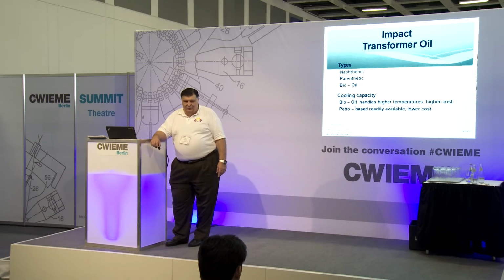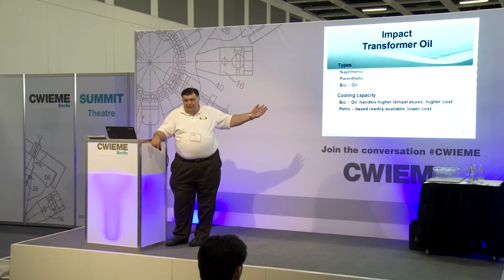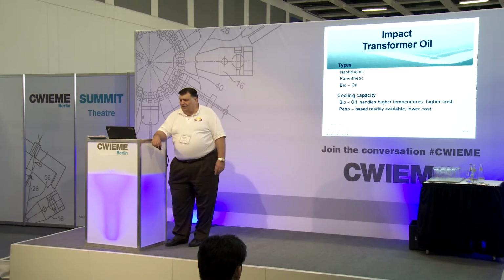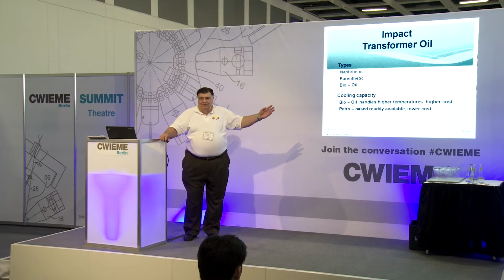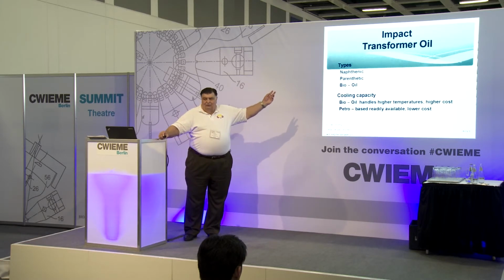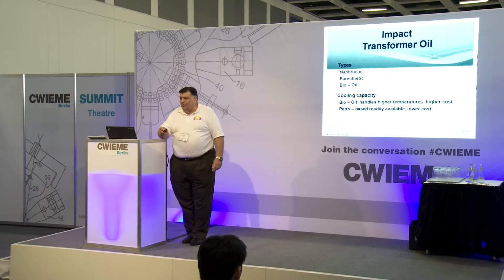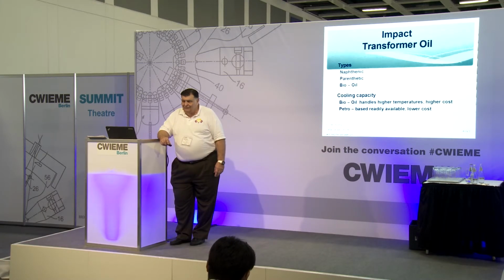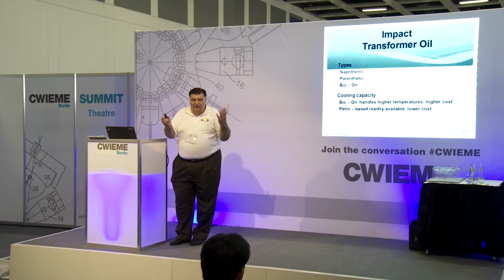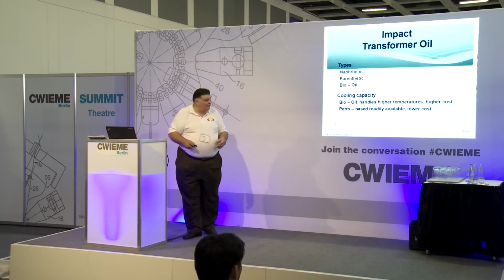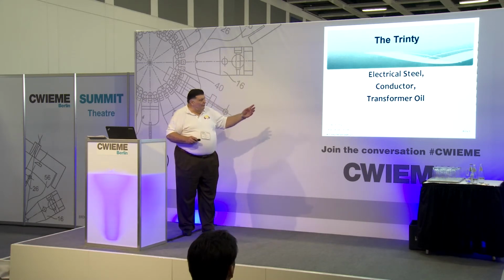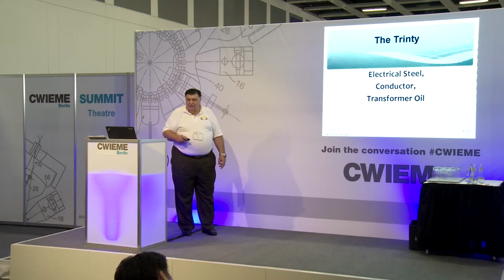So is there a trade-off in the cost of the bio-oils versus the others to have the higher operating temperatures and not increase the total amount of oil you use? Or do you increase the amount of oil on the others and increase your tank size? Again, it goes back to what conductor you are going to use, and what grain-oriented electrical steel or amorphous you can get. So you have to continually juggle these and the cost of all of them. Electrical steel, conductor, and transformer oil are the Trinity.